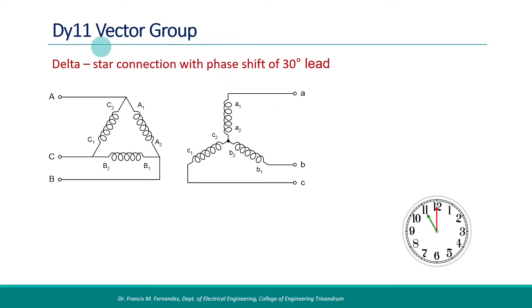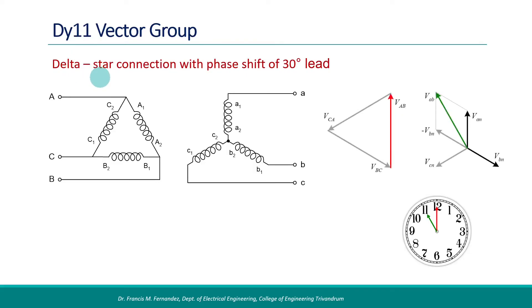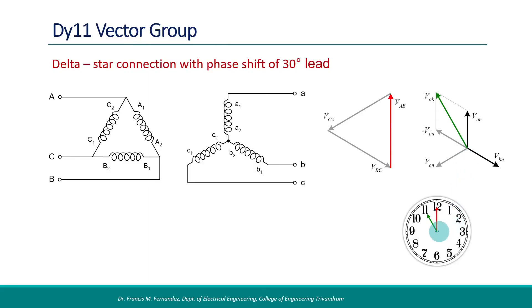The last one in this listing is the DY11 vector group. The primary is delta connected and the secondary is star connected. In the phasor diagram, the voltage induced in winding A of the secondary will be in phase with the primary line voltage. The line voltage VAB in the secondary is obtained by VA minus VB. Finally, the line voltage is leading by 30 degrees from the corresponding primary voltage — the 11 o'clock position matches here also. The simplified connection diagram and the displacement diagram are shown.